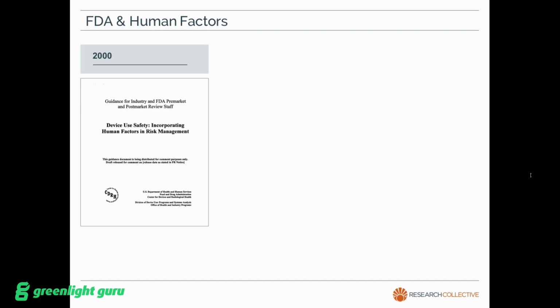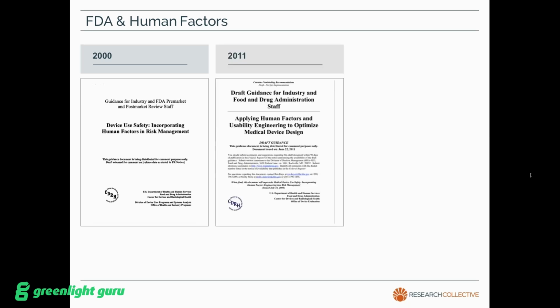And they recognized the benefits of applying things like human factors to the design of medical equipment for many years. In 2000, CDRH released this guidance document describing how human factors should be incorporated into risk management. Over the next 10 years, the human factors group was established within FDA, and so did the demand on medical device manufacturers to provide evidence of a human factors process in their application for PMAs and 510Ks and so on.